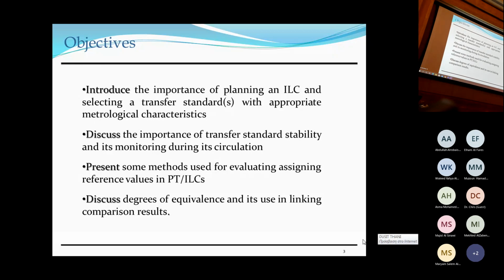For a calibration lab, it's more difficult because you have a transfer standard, which you have to make sure is stable, and in order to make sure that it's stable, it has to be measured twice at least. Whereas with a sample, you have 10 pieces of a sample, you make your measurements, you send the results, you throw the sample away. That's it. So the situation is very different, and that's why there are not that many PT providers for calibration, by the way. There's one in Dubai also, which is a representative of an Australian company.